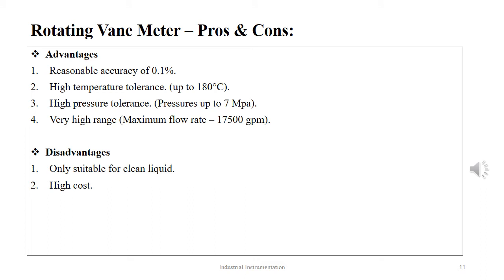The advantages of the rotating vanes meter are: they offer reasonable accuracy that is ±0.1%, very high temperature tolerance up to 180 degrees Celsius, very high pressure tolerance up to 7 MPa, and wide range of operation up to 17,500 gallons per minute.